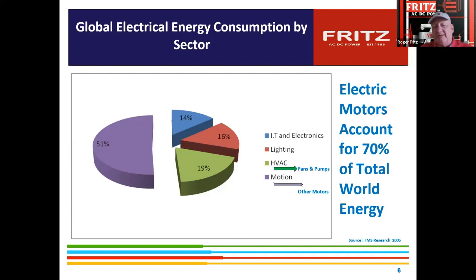But the main impact in HVAC is the chillers, the fans, the pumps, those big chiller compressors. Those need to be evaluated if they don't have drive controls. And then on the motion side, there's a lot of energy you can save also, for other reasons. By just slowing a conveyor down, you really didn't need to move the material quite that fast, or maybe it's a press machine that has variable hydraulics.